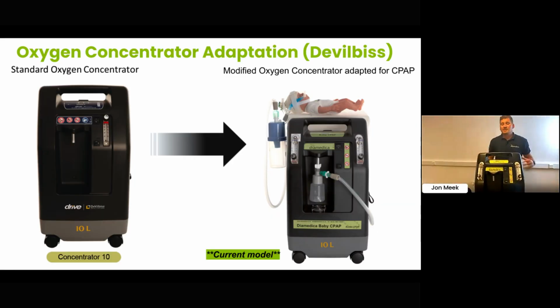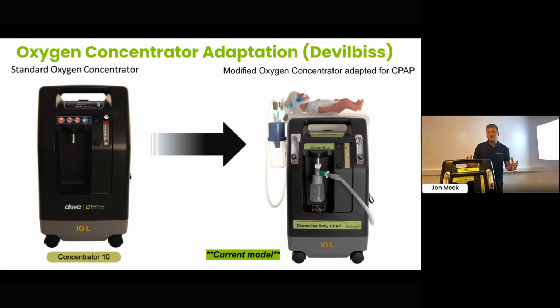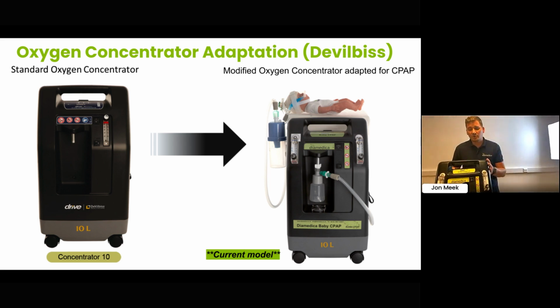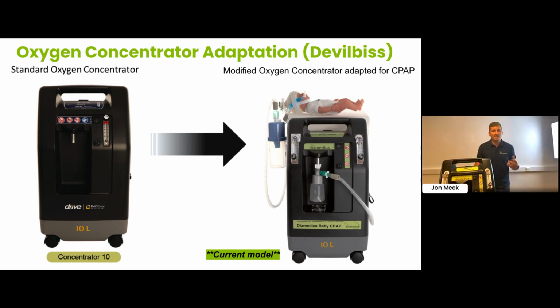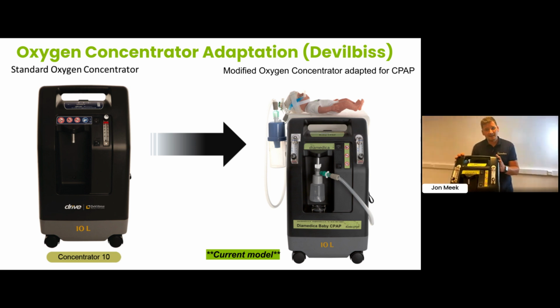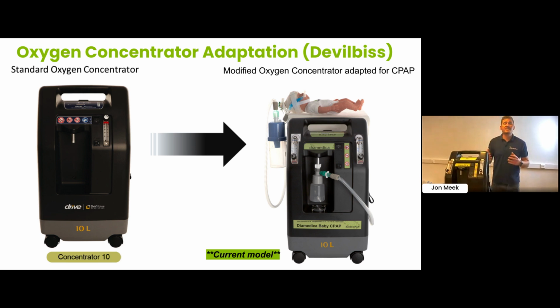Okay, so as I said before, we've designed our CPAP to generate its own oxygen and medical air. Going forward, we have two ranges. We have a CPAP 10 that has two flow meters from 0 to 5, so you can generate a maximum of 10 liters a minute, 5 of air and 5 of oxygen. We also have a CPAP 20, which provides 10 liters of air and 10 liters of oxygen, giving a combined flow rate of 20 liters a minute.